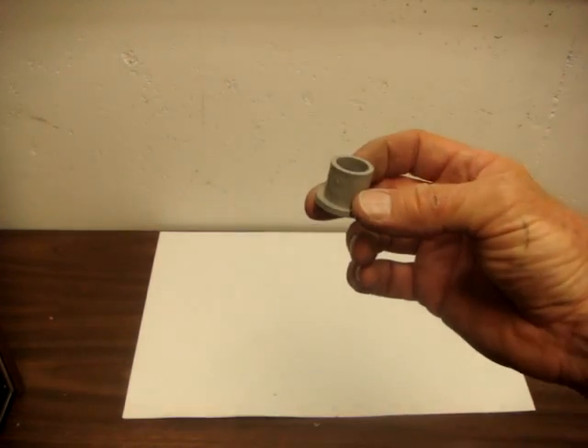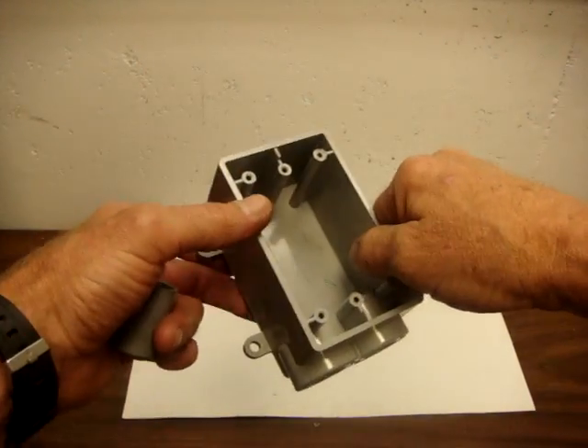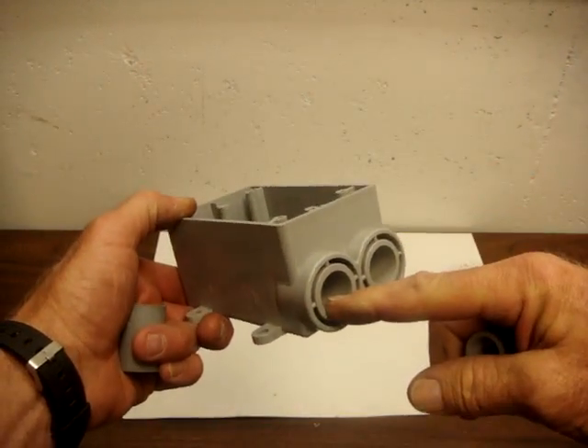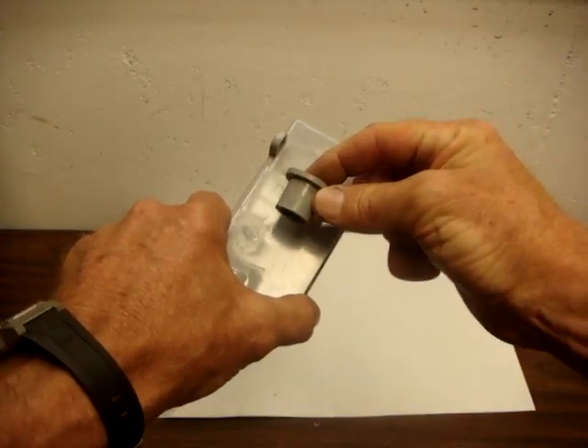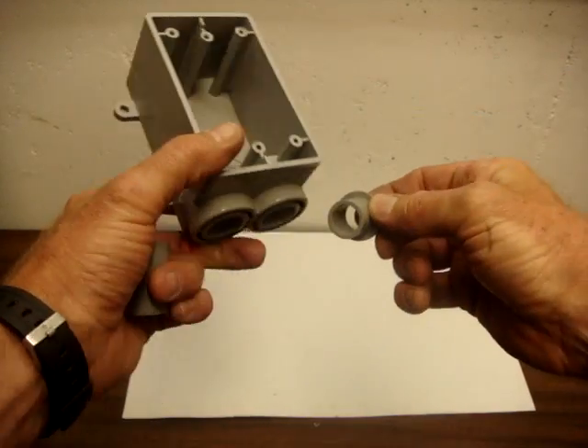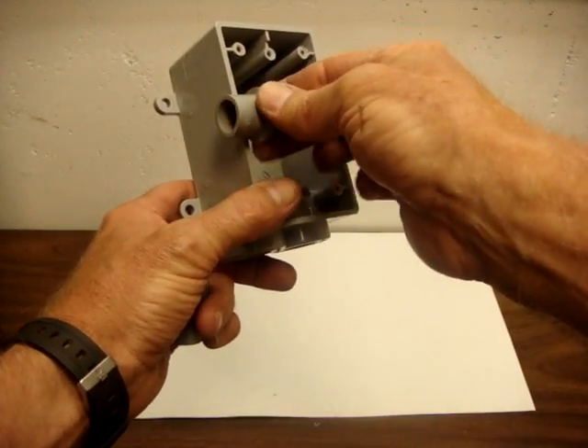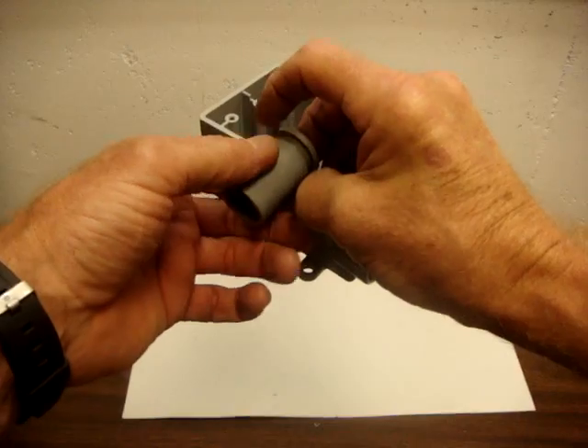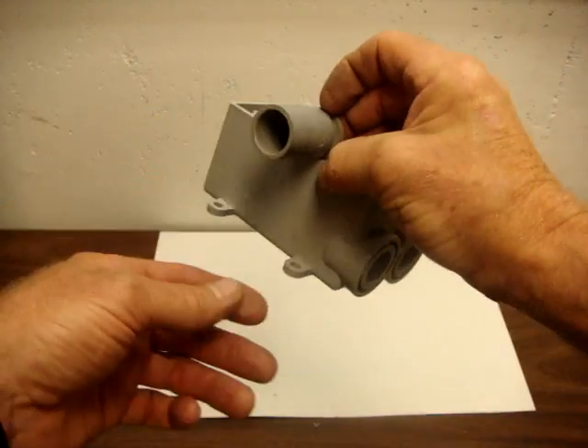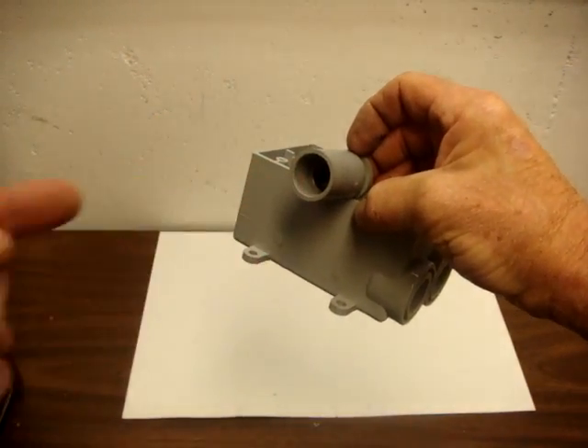This is a PVC box adapter used in conjunction with a coupling. In this particular case, this box has two built-in hubs. But if I wanted to come off the side, I would drill a hole this size, put glue on this, stick it through the hole, and then put glue on here. This becomes a sort of hub where you can come off of the box from the side, the back, or wherever you need to approach it from.